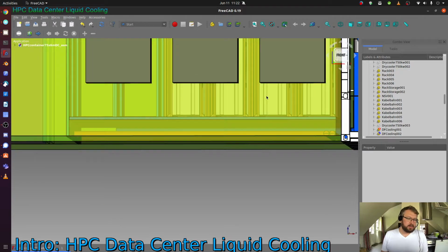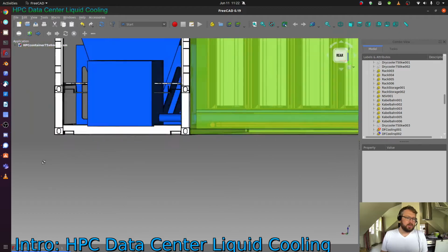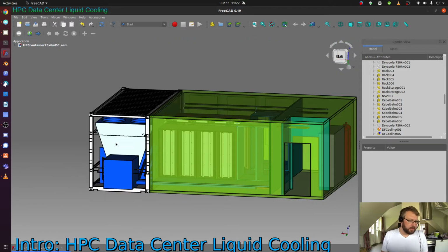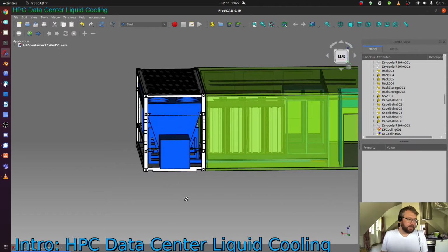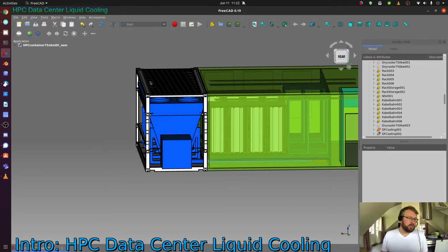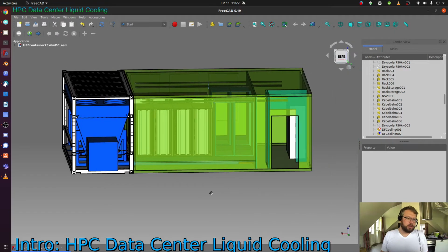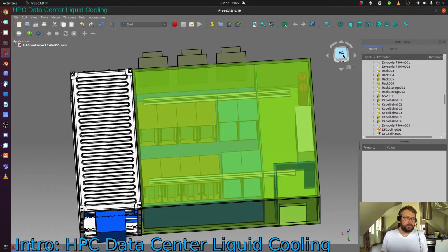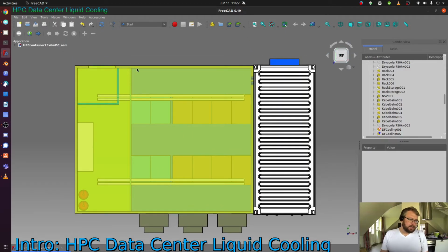So the energy is transferred down into the piping and then into the dry cooler, with an outside dry cooler pump box that is protected and has a redundant pump setup, and then moved into the dry cooler and moved outside to the air. The whole setup, if you look at this from the top, has an IT space with the raised floor and a technical room with the main distribution, the fire extinguisher system, and connection to the outside world, to the fiber.